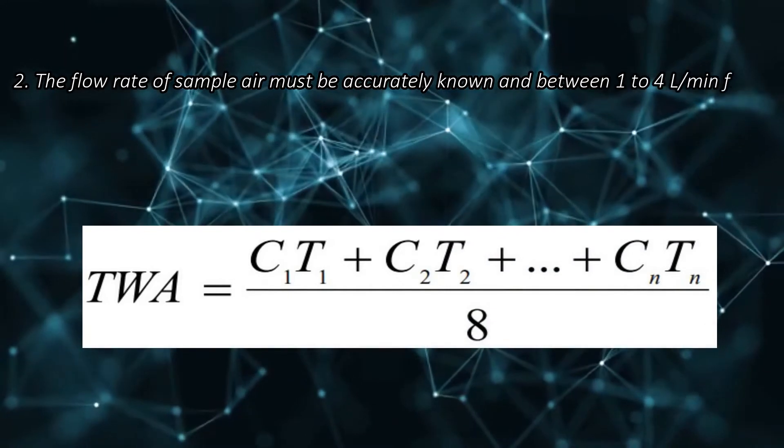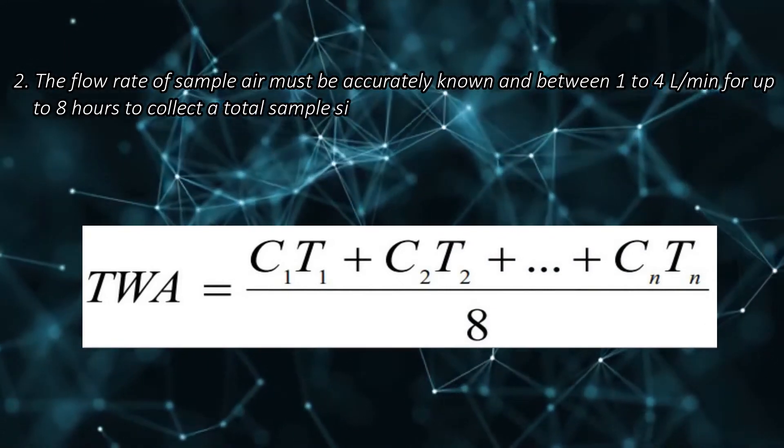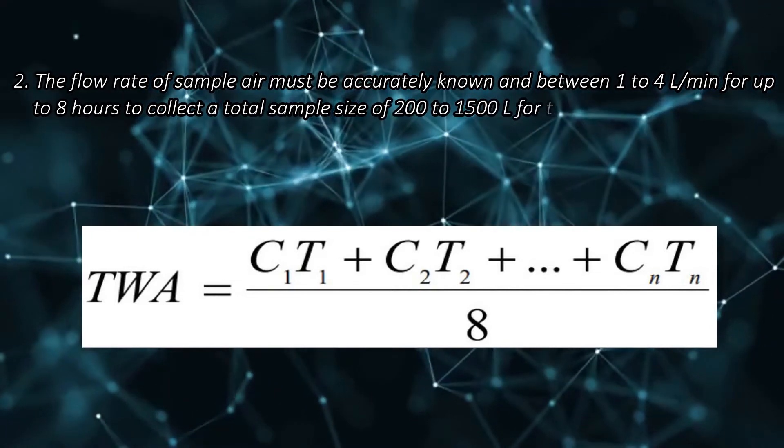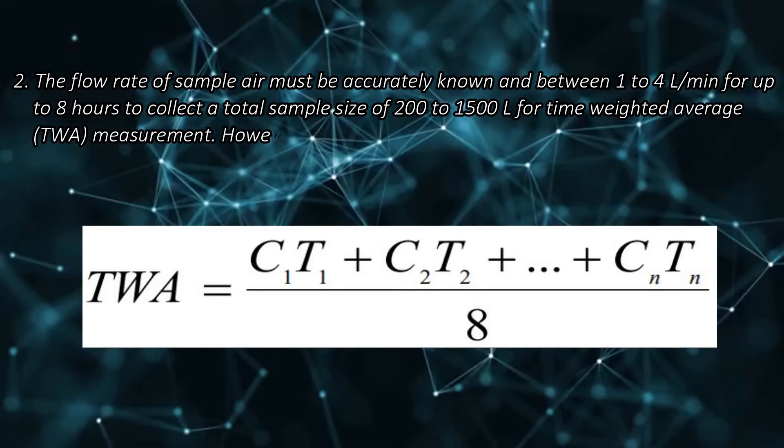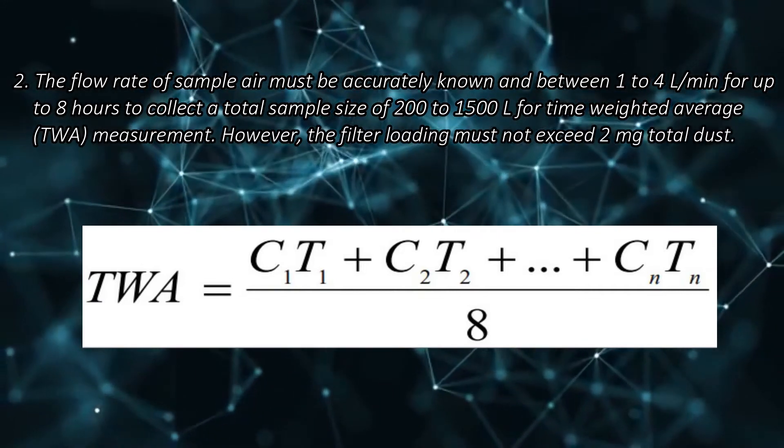The flow rate of sample air must be accurately known and between 1 to 4 litres per minute for up to 8 hours to collect a total sample size of 200 to 1500 litres for time weighted average TWA measurement. However, the filter loading must not exceed 2 milligrams total dust.